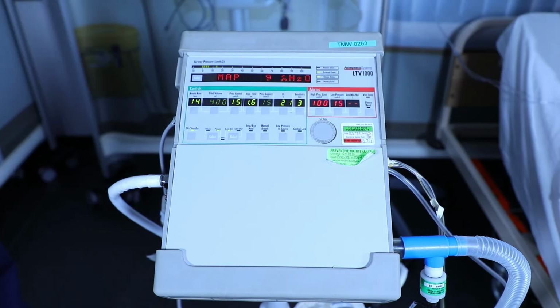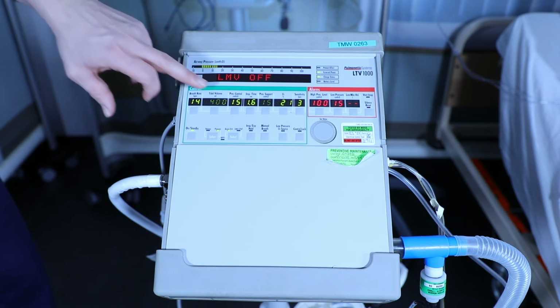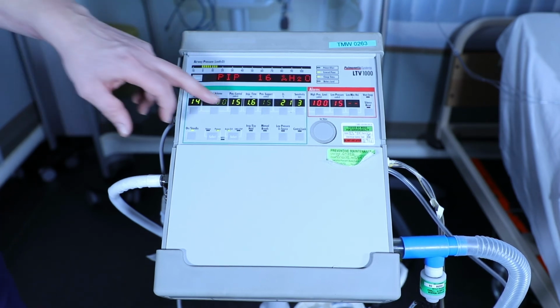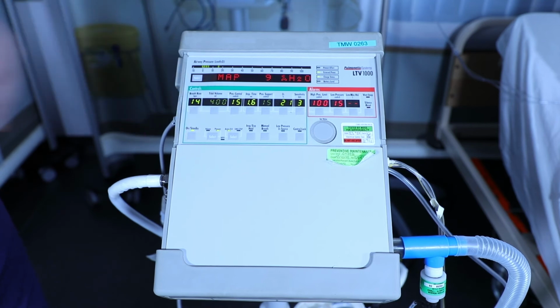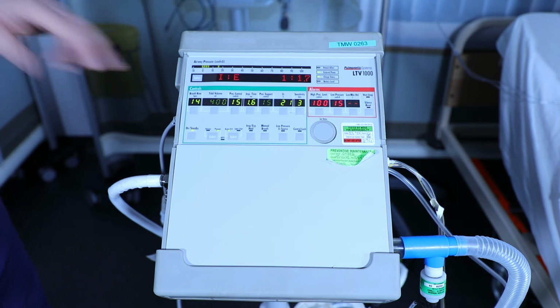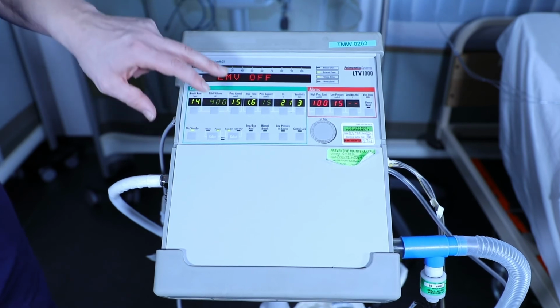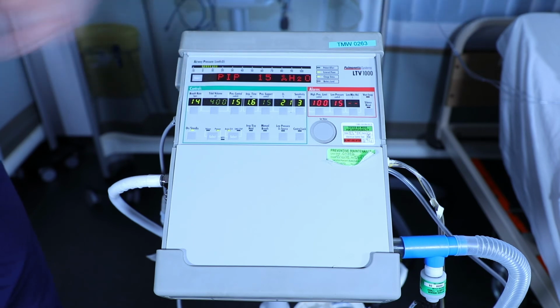Because of the way that the PEEP is set on this via an external PEEP valve, we have to take into consideration that when we transfer from a regular hospital ventilator, most of these ventilators have internal PEEP. So in order to do the transfer appropriately, we must add the PEEP that's set on the hospital ventilator to the pressure that's also set. So we set above PEEP. An example of this: if the patient was on 10 of pressure control and 5 of PEEP in the hospital, we would then set our pressure control to 15 and also set our PEEP to 5 via the PEEP valve.